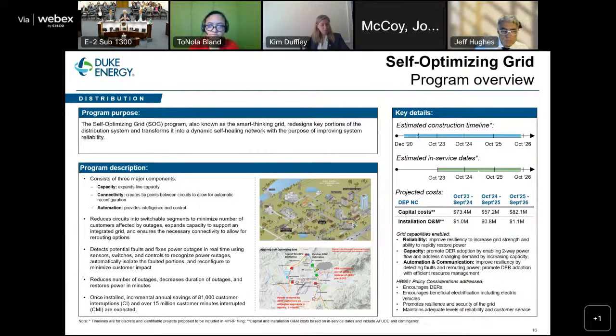They have to be physically connected with a strong tie to transfer load back and forth in outage or fault conditions. And lastly, automation and communication. This is about applying those intelligent switches out on the grid, also the automation software back in our control centers that provides command and control, usually in less than a minute when it detects a fault situation, to restore as many customers as possible.